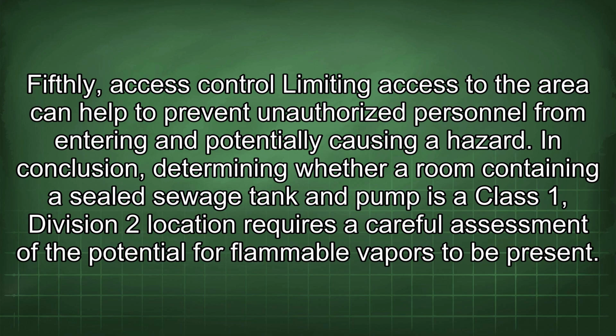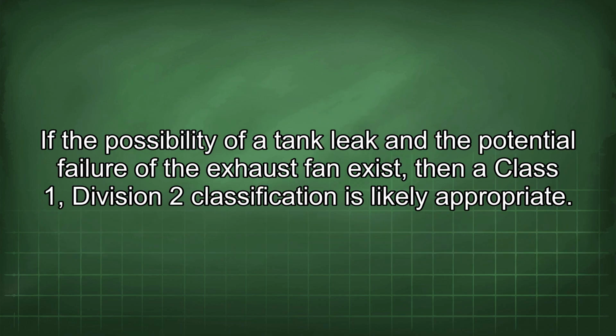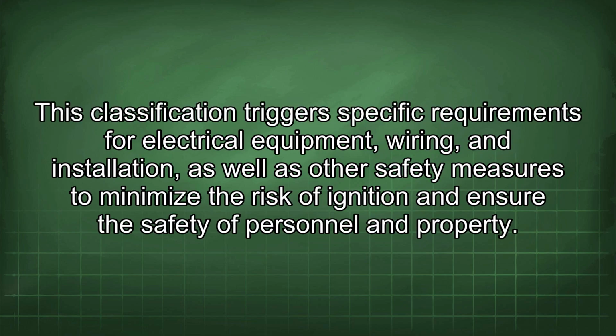In conclusion, determining whether a room containing a sealed sewage tank and pump is a Class 1, Division 2 location requires a careful assessment of the potential for flammable vapors to be present. If the possibility of a tank leak and the potential failure of the exhaust fan exist, then a Class 1, Division 2 classification is likely appropriate. This classification triggers specific requirements for electrical equipment, wiring, and installation, as well as other safety measures to minimize the risk of ignition and ensure the safety of personnel and property.